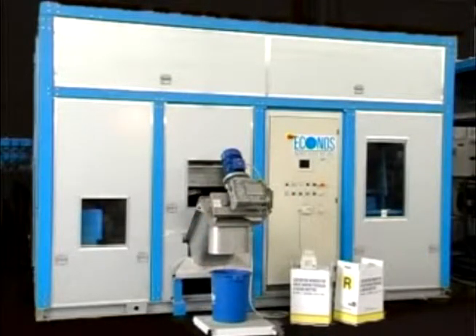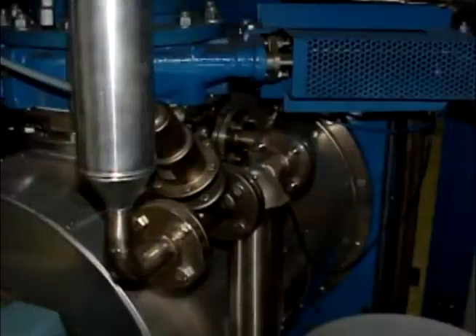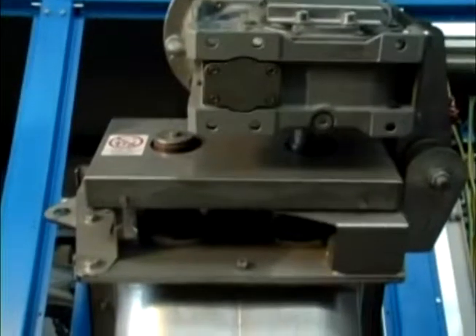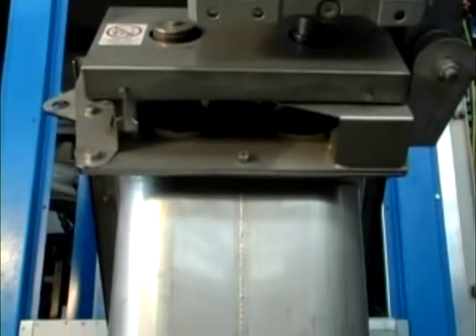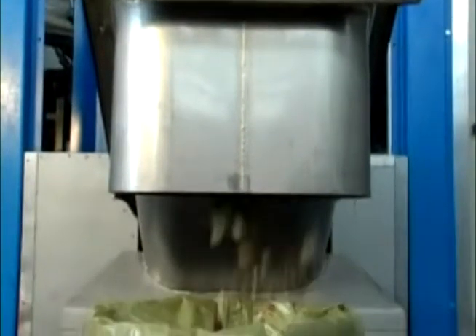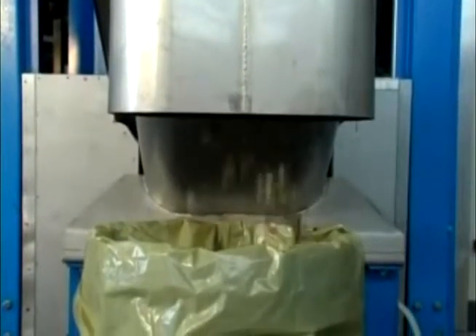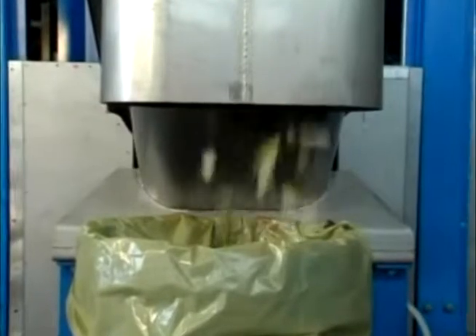The extremities of the sterilization chamber are controlled by a loading guillotine valve and a discharge door on the front side. Both closures guarantee a perfect seal to the pressure. At the end of the process, the discharge door opens, dropping the sterilized material into the cochlea, which conveys it to the exit.